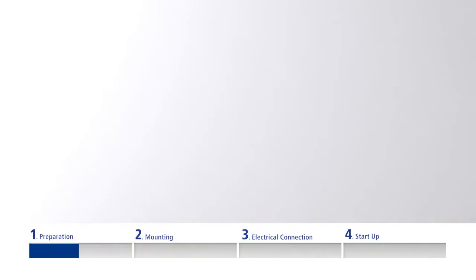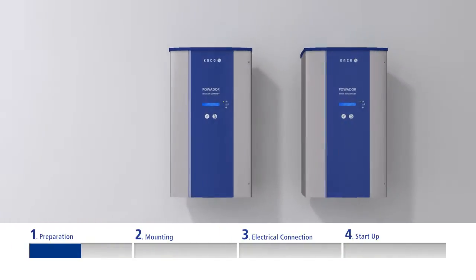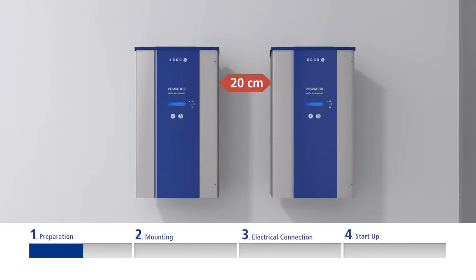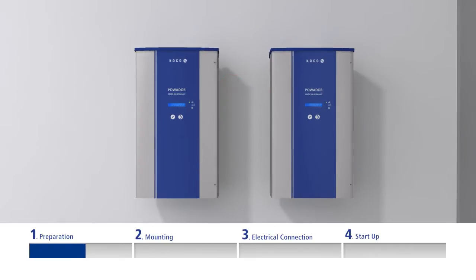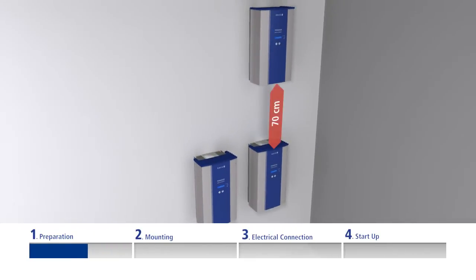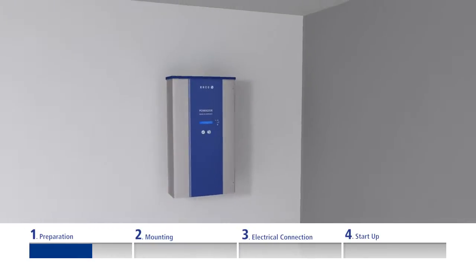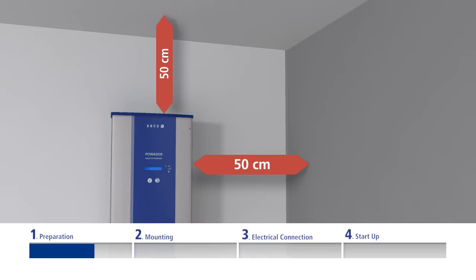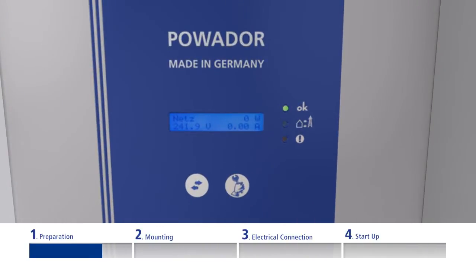Maintain the following minimum clearances around the unit: 20cm between inverters mounted side by side, 70cm between inverters mounted above each other, 50cm to the floor or ceiling, to shelves, cabinets or similar. When arranging the inverters, please also ensure that the inverter displays will be clearly visible afterwards.